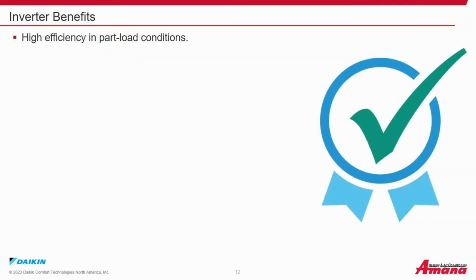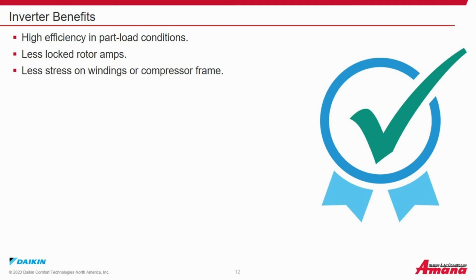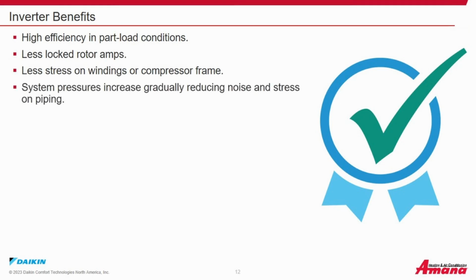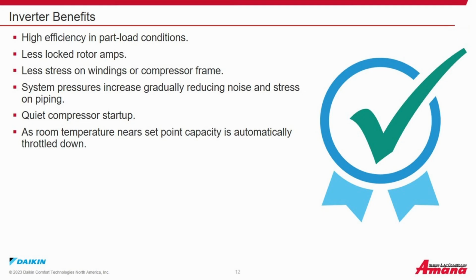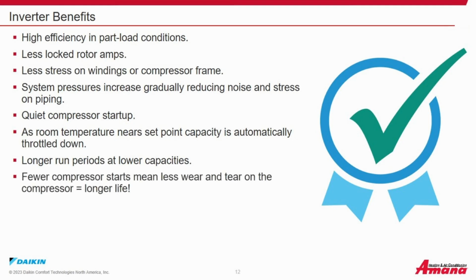Inverter benefits. High efficiency in part load conditions. Less locked rotor amps. Less stress on the windings or the compressor frame. System pressures increase gradually, reducing noise and stress on piping. Quiet compressor startup. As room temperature nears a set point, capacity is automatically throttled down. Fewer compressor starts means less wear and tear on the compressor, which equals longer life.